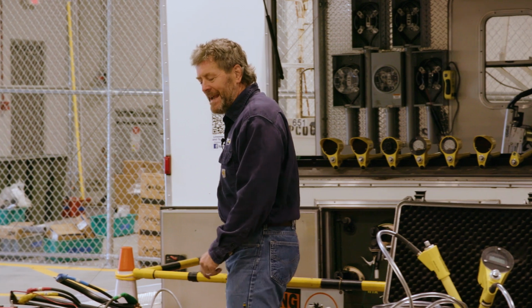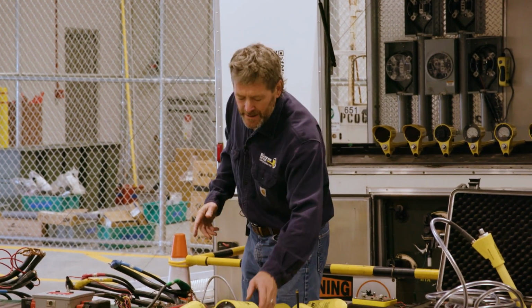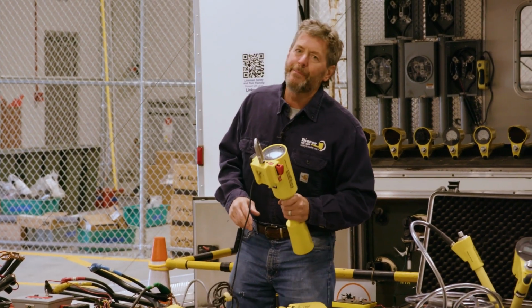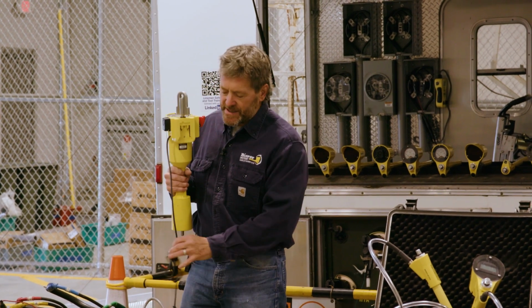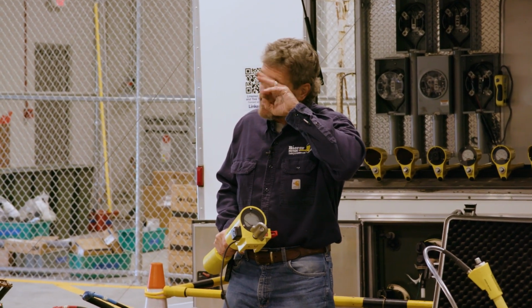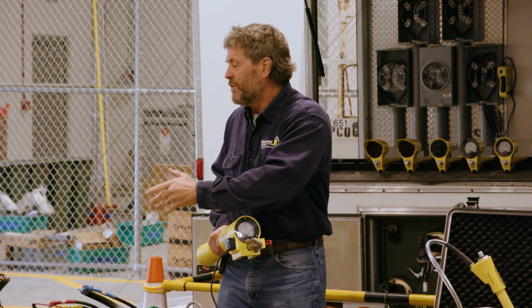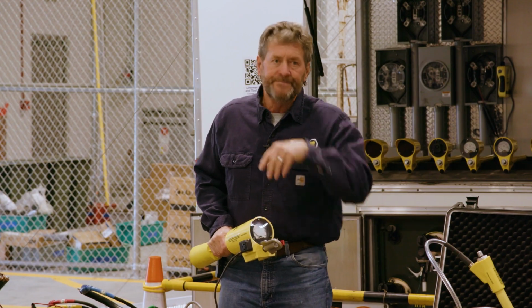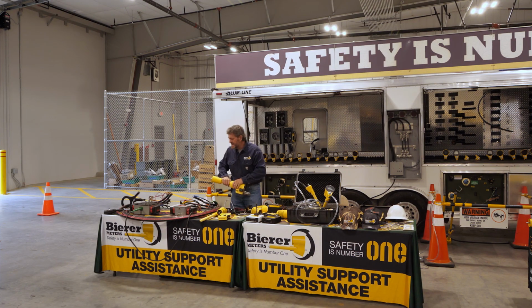They liked that. Anyways, real quick, high potter. This is a high pot tool, and you can use this quickly on new construction or existing to verify if the span between transformers is good or bad. You simply use an 18-volt Milwaukee or Makita, turn it on.